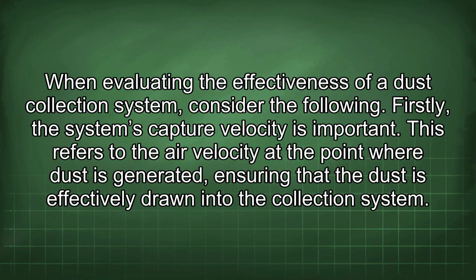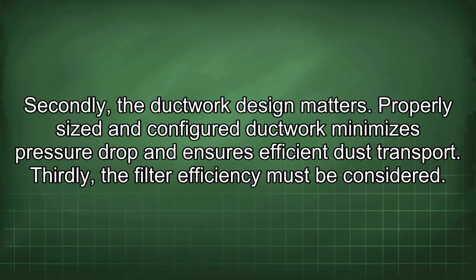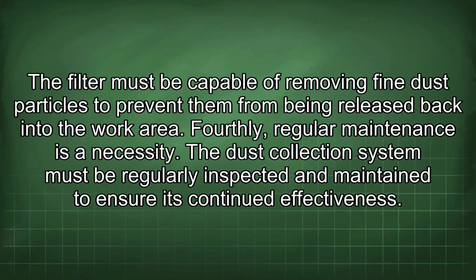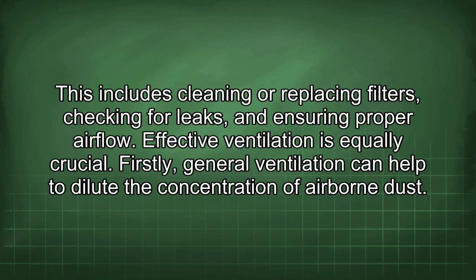When evaluating the effectiveness of a dust collection system, consider the following. Firstly, the system's capture velocity is important. This refers to the air velocity at the point where dust is generated, ensuring that the dust is effectively drawn into the collection system. Secondly, the ductwork design matters. Properly sized and configured ductwork minimizes pressure drop and ensures efficient dust transport. Thirdly, the filter efficiency must be considered. The filter must be capable of removing fine dust particles to prevent them from being released back into the work area. Fourthly, regular maintenance is a necessity. The dust collection system must be regularly inspected and maintained to ensure its continued effectiveness. This includes cleaning or replacing filters, checking for leaks, and ensuring proper airflow.